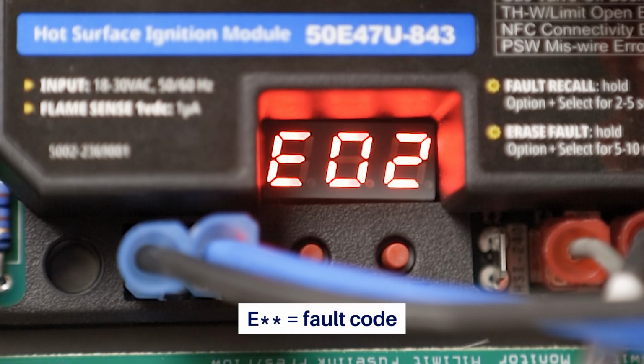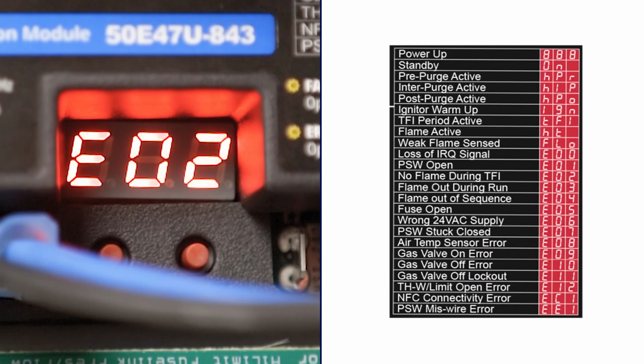If any errors occur during a cycle, a fault code will indicate the error. For an active error condition, the display will show an E followed by 2 numbers. An error code E02 showing indicates an active error. The fault code label on the cover of the 50E47U-843 indicates there was no flame during a trial for ignition. Up to 5 fault codes can be stored in the sequence they occurred.